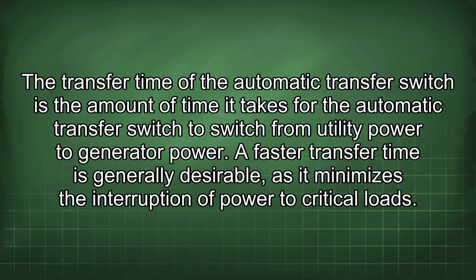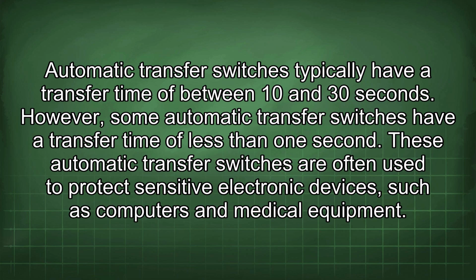The transfer time of the automatic transfer switch is the amount of time it takes for the automatic transfer switch to switch from utility power to generator power. A faster transfer time is generally desirable, as it minimizes the interruption of power to critical loads. Automatic transfer switches typically have a transfer time of between 10 and 30 seconds. However, some automatic transfer switches have a transfer time of less than 1 second. These automatic transfer switches are often used to protect sensitive electronic devices, such as computers and medical equipment.